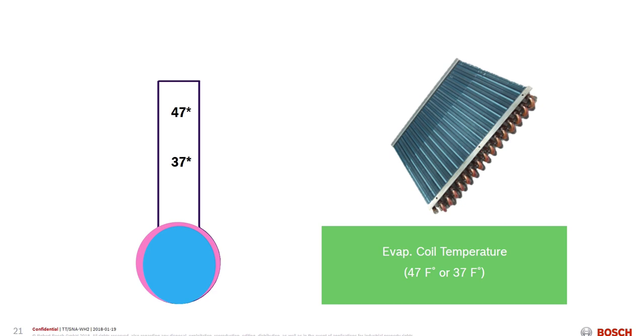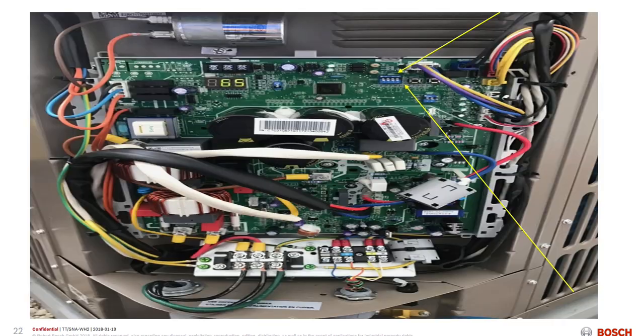At that particular time, if I need a little bit colder coil, if I need a little bit more latent heat removed, I can turn the unit off, flip the switch, and change that logic on the unit to a 37 degree logic. We call that enhanced mode. I didn't change anything in the refrigeration process, didn't change anything with the indoor air moving machine, just changed the switch. The switch right there is indicated by that yellow line.